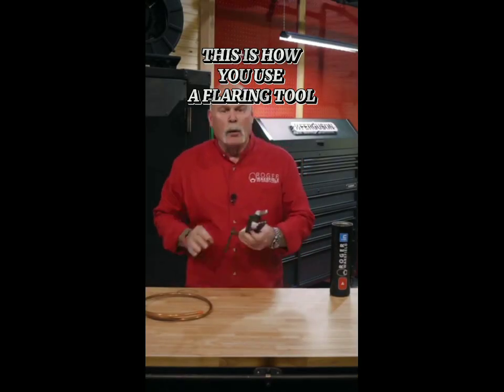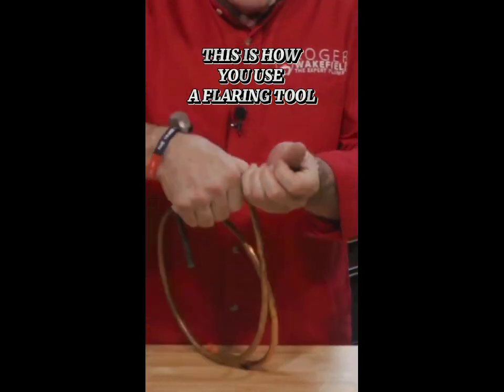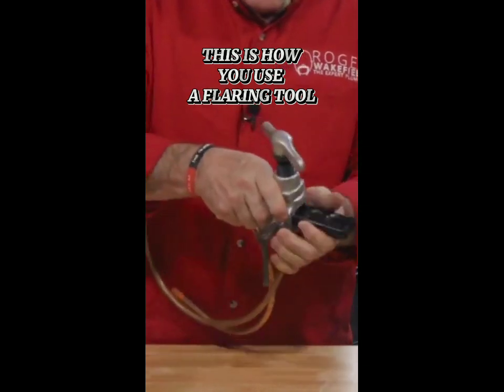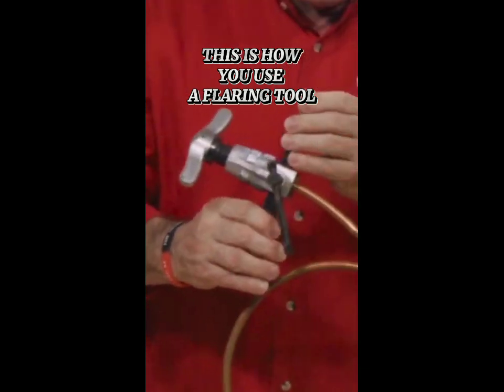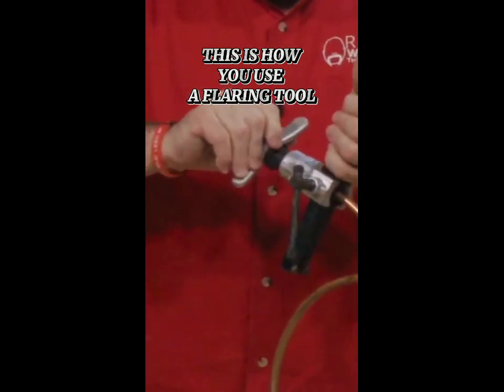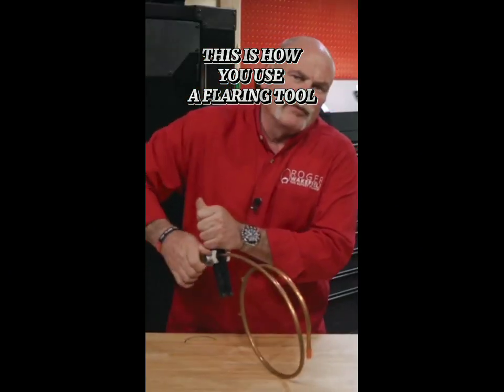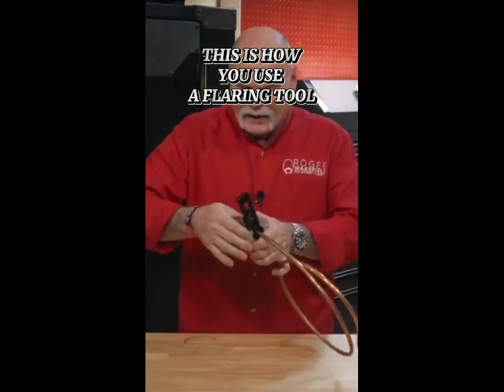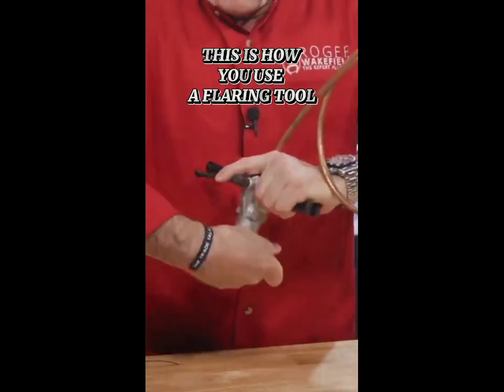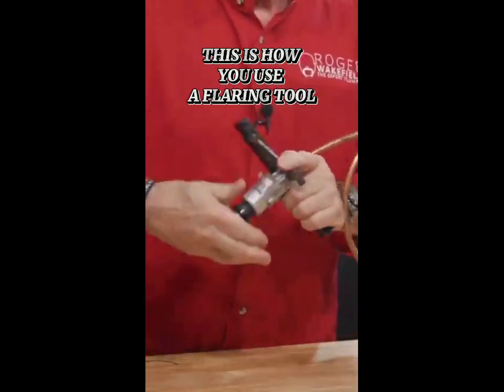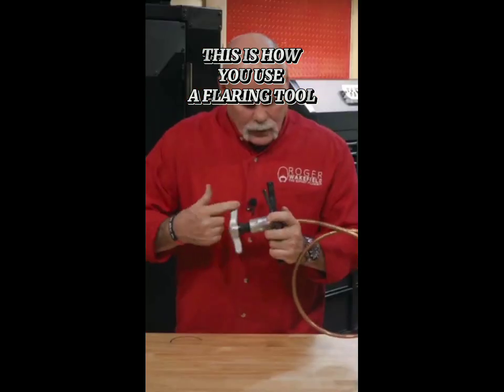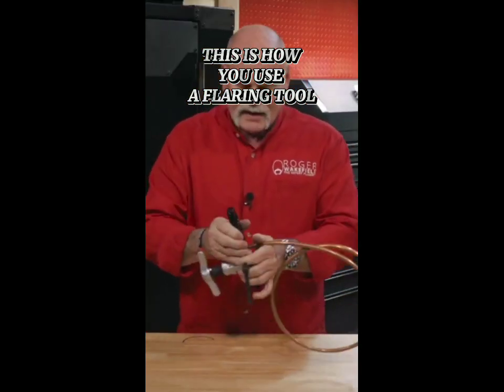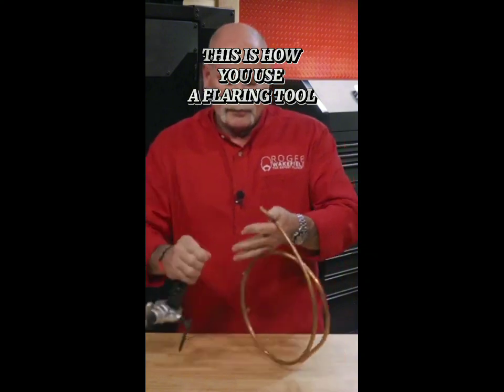Slide it down to where you can open it up. Bring it up where it's flush with the top, and then slide this down. Once you get it in position, tighten it up in the right spot. It goes down into the copper. Now you spread this up. That keeps it from pulling apart and opening up, where it can slide down and then start flaring. Now once it starts clicking, it's not pushing in anymore.